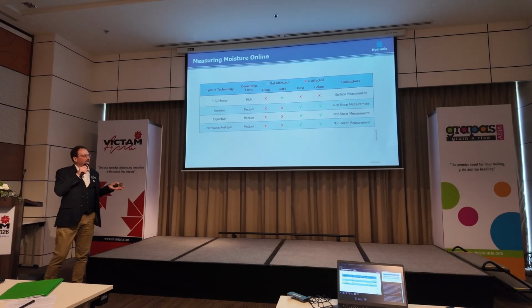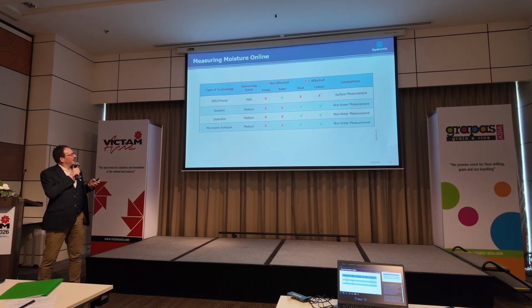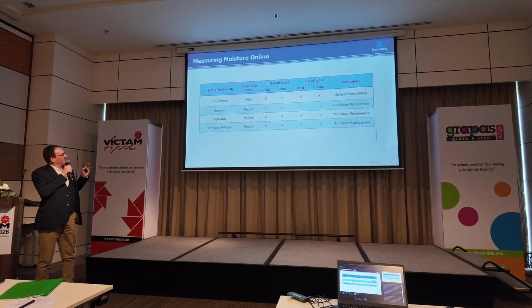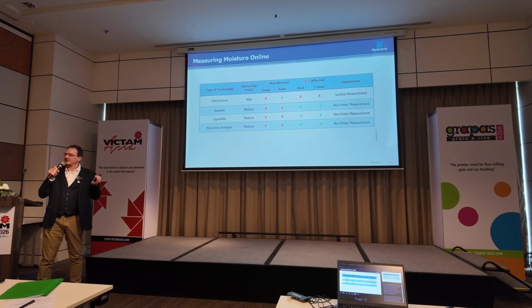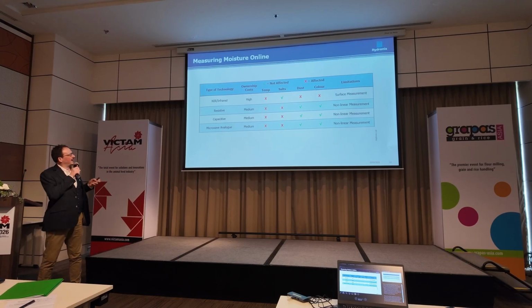So measuring moisture online, what are the options? We have a few different options. There's a lot of different ways to crack eggs and cook coconuts. Near infrared, or NIR, tends to be quite high cost. They do give you a lot of different measurements, so you can get fat content and protein content. But they do tend to be affected by the process temperatures, and by dust and colour changes. They don't tend to be too affected by salts because it's one of the parameters, but they are only a surface measurement, so they tend to be an optical measurement. If you've got material on a conveyor or something like that, then you only ever get the top level. If it's hot and it's flash evaporating, then that can cause problems to that measurement.